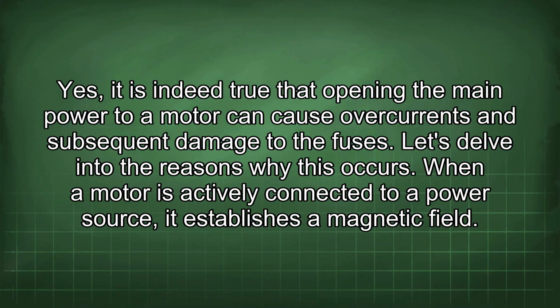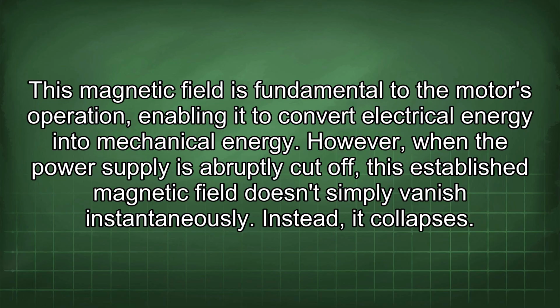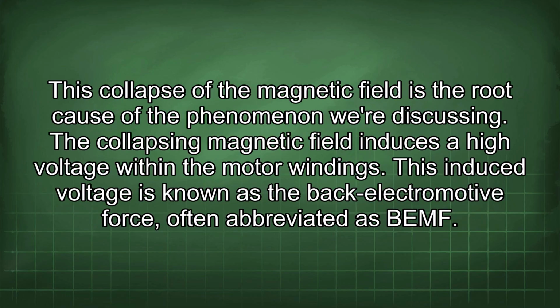Yes, it is indeed true that opening the main power to a motor can cause overcurrents and subsequent damage to the fuses. Let's delve into the reasons why this occurs. When a motor is actively connected to a power source, it establishes a magnetic field. This magnetic field is fundamental to the motor's operation, enabling it to convert electrical energy into mechanical energy. However, when the power supply is abruptly cut off, this established magnetic field doesn't simply vanish instantaneously. Instead, it collapses. This collapse of the magnetic field is the root cause of the phenomenon we're discussing.